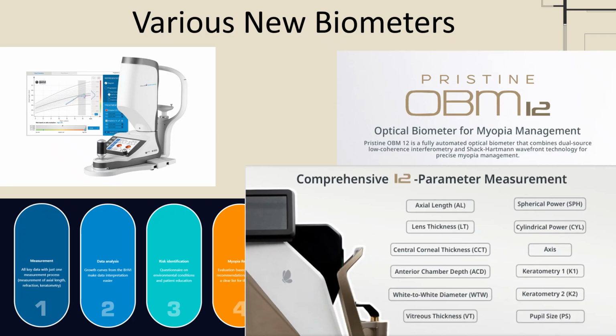It will give you axial length, spherical lens thickness, cylindrical power, CCT, which means pachymetry, anterior chamber depth. It will give you keratometry. It will give you white to white diameter, pupillary size. So essentially what they are doing is, they are trying to go into myopia. You don't need pupil size if you are doing biometry. Your biometer will not do it, but your topographer will do it. Even the Vision X90 auto ref will also do pupil size.